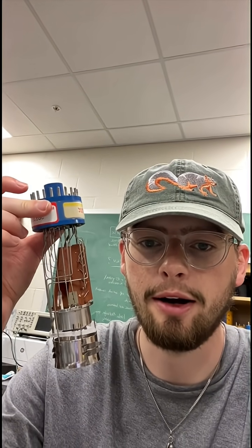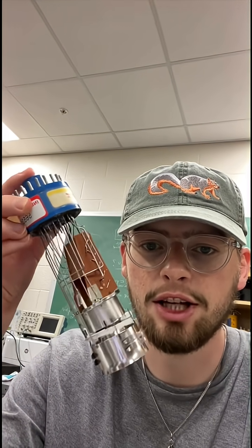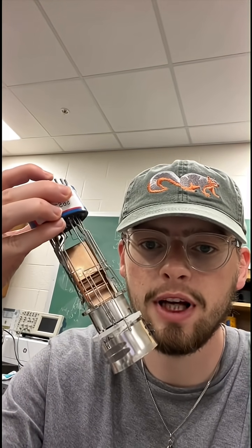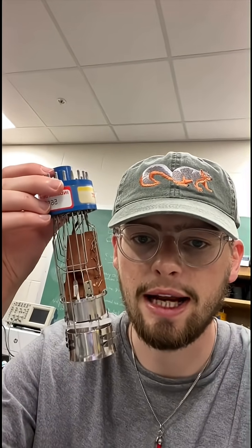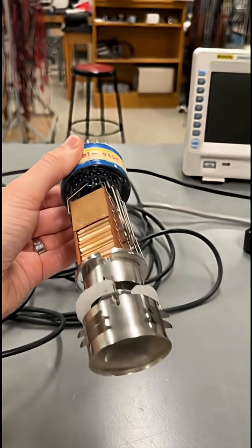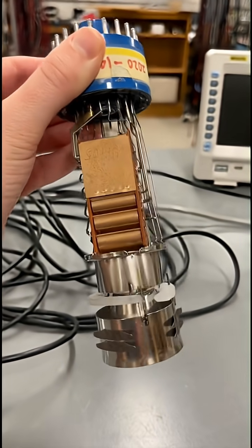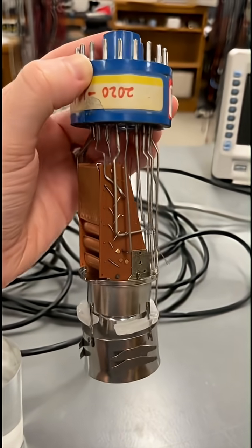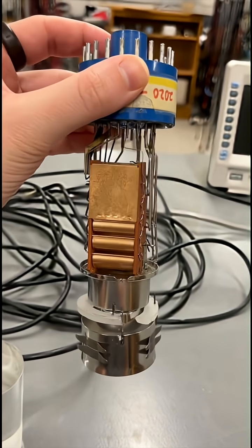the photomultiplier tube. And essentially this thing is like a reverse flashlight, and this is one that has actually had the glass shell removed. Normally these are encased in glass and kept under a vacuum inside of the glass. But starting at the bottom, there will be a material which, when the light from the scintillator crystal hits it, emits a few electrons. And then those electrons, because this is held at a high voltage, essentially get sucked up like a vacuum through this system.